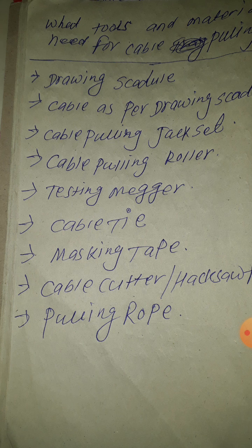From the electrical room to some equipment, SMDB and MDB, at pulling time, and this is also high level pulling, and pulling again for a return is a big issue. So this is double main power. So first check the cable properly, whether its condition is good or not. You can check with a multimeter, IR insulation resistance plus core to core resistance. Core to core means red to yellow, yellow to blue, and yellow to black, like that. If we have a 4 core cable, check all cores. If 3 core, check all cores, and the insulation also. That time you need to measure, at IR testing time.